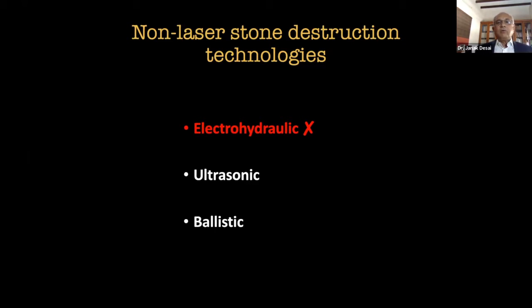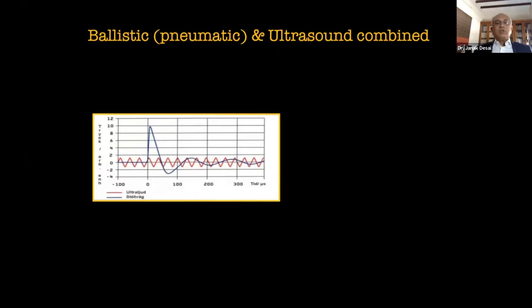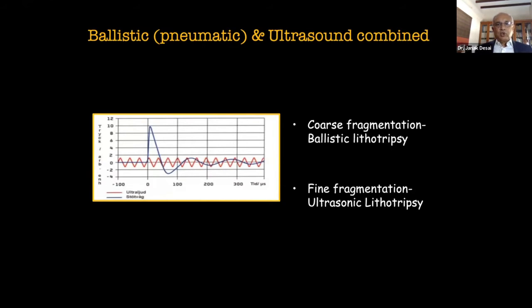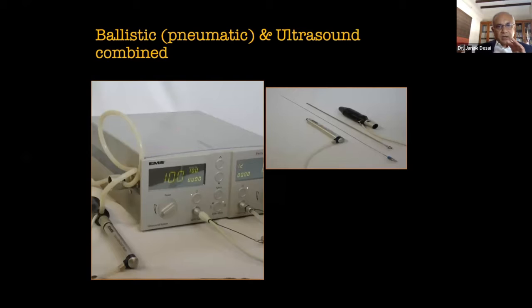I already told you it started off with ultrasonic. Ballistic was added later on, and then comes the combination. In the combination, the coarse fragments are handled with ballistic, which is fast, but a little flying away of fragments is possible. And the fine fragments are handled with ultrasonic. So then from the lithoclast comes the lithoclast master, which is this device. A little bit of a disadvantage, which down the road we all realized, was that the pneumatic probe was going through the ultrasonic probe, so it was occupying space. So when you had both in position and used the ultrasonic, larger fragments could not be sucked out because the ballistic probe was occupying space within the ultrasound.